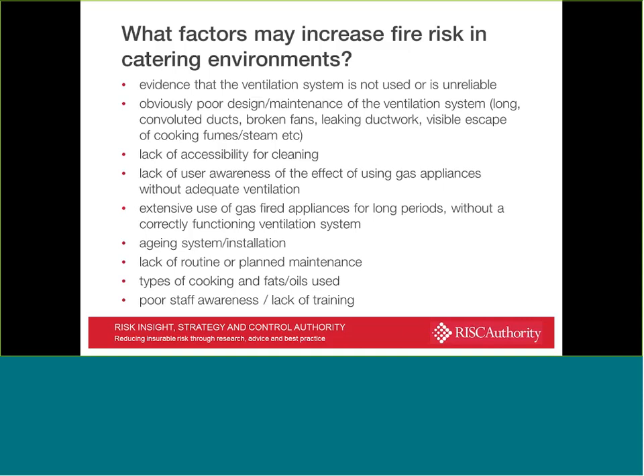But we also have to look at the types of cooking oils and fats that might be used, or even the types of cooking. For example, different styles of cooking will produce different types of greases or deposits within the extract ductwork. Thai cooking oil and Chinese food create a syrup-like grease that can be very, very difficult to remove. If you're cooking or charbroiling meat, for example, you get large quantities of grease which will easily bind to the surface of the ductwork, which then makes it easier for additional layers to adhere, and you end up with a fairly unpleasant thick build-up. And of course, you may end up with other deposits from overcooked meats and such like, in terms of ash or grease from the process.